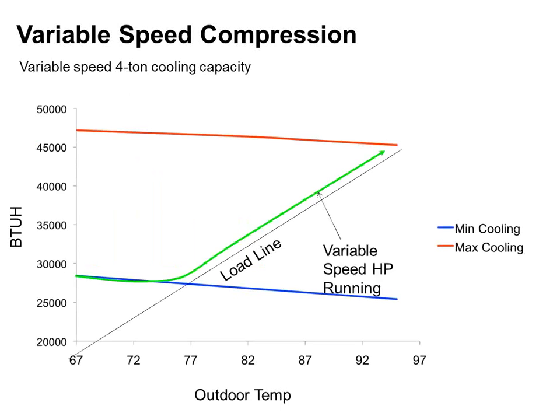Just to give you a couple examples, very similar to what we did on the heating side. Here's a cooling example, but the load of my building goes the opposite way. It's still that black line. It goes the other direction. Right when it's 70 degrees outside, I don't need any cooling really. And then as it moves along, it's hotter and hotter outside. I need more and more BTUs. And a variable speed system can handle anything in between.